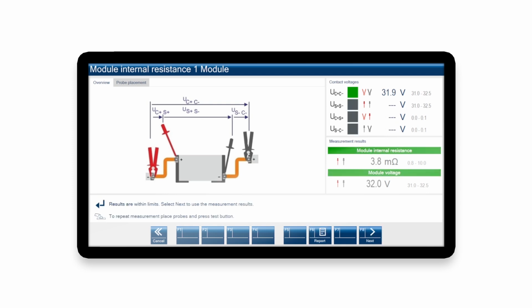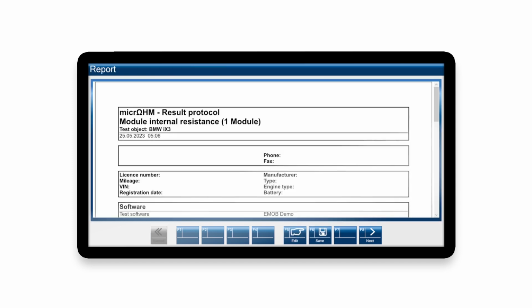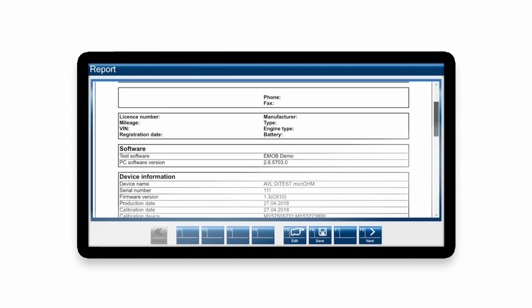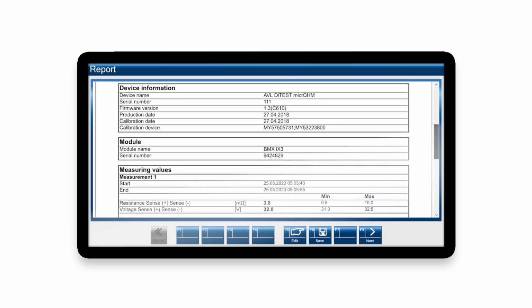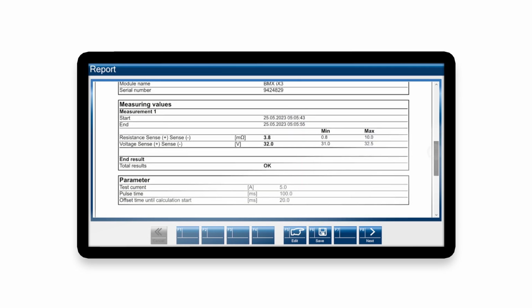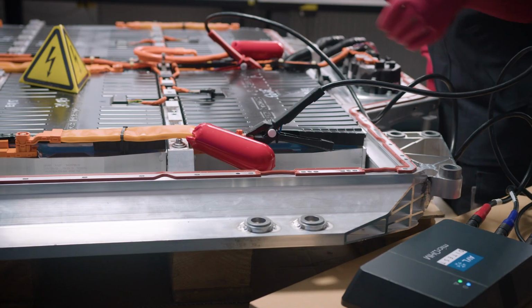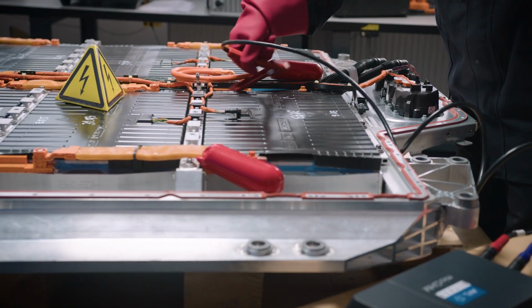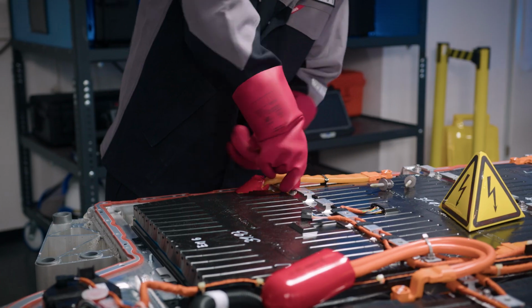Increased resistance can have various causes. With the contact measurement mode, 0.1 micrOHM resolution, you can detect defective bus bars and incorrectly torqued bolts. The internal resistance measurement mode, 100 micrOHM resolution, detects defective modules. All parameters and results are automatically documented. This data helps determine if the module can be reused or needs recycling. Now we can remove the defective module.